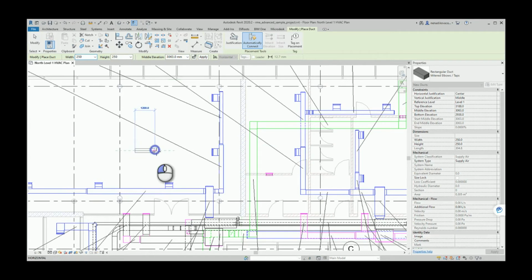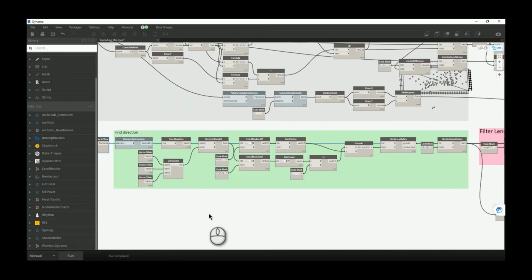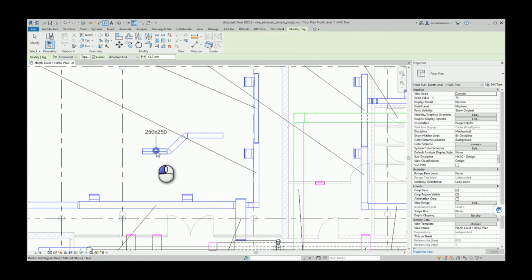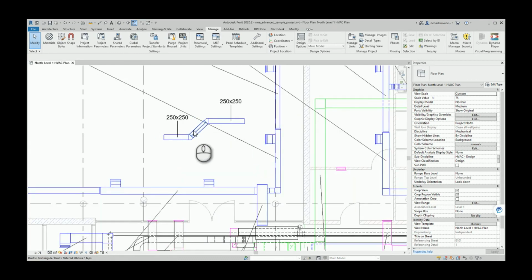So also in the previous script, when you have maybe some route which will go like this, the script was unable to deal with this kind of direction. It is not parallel to x, it is not parallel to y, does not have a z direction, so it is some custom angle regarding the x and y plane. Now I did choose to solve this in a very easy way. I will just ignore those directions. I will filter all directions which have some custom angle between 0 and 90. My idea was probably on some plane you will have maybe 1, 2, 5, 10 times this kind of situation, and if you tag this duct over here, and this duct over here, I mean you don't even need to tag this duct over here, but again, if you did tag like 80 different ducts, okay, so you will invest maybe 1 or 2 minutes after you tag all elements to also include those ducts. So that was my solution.